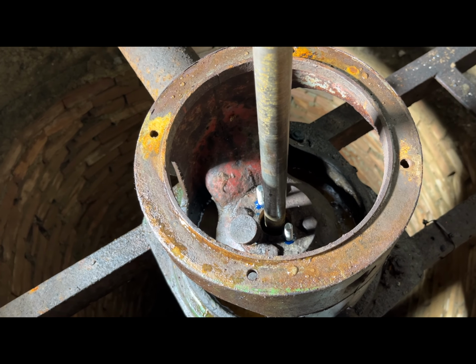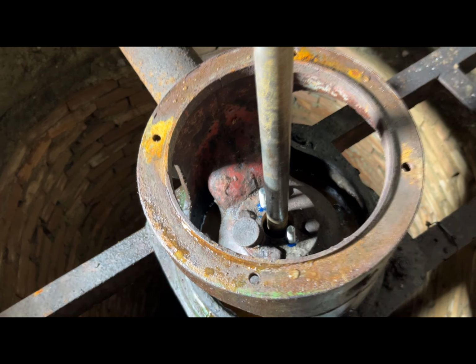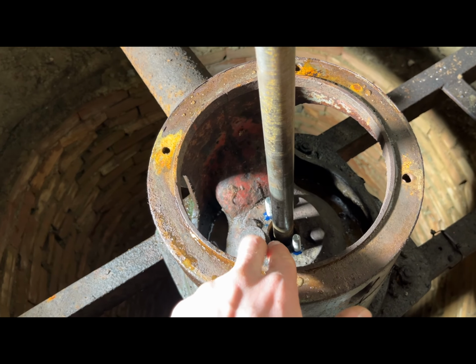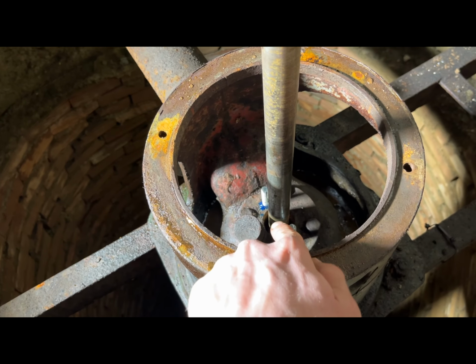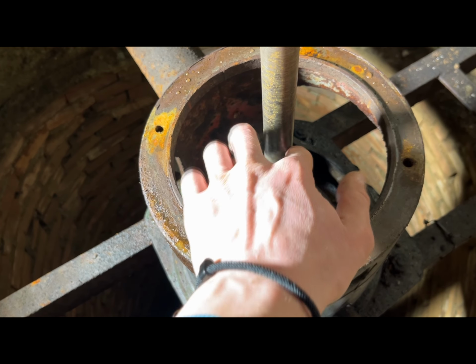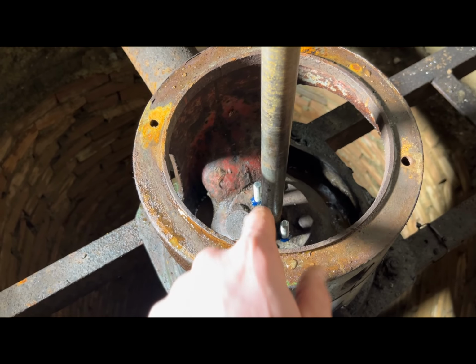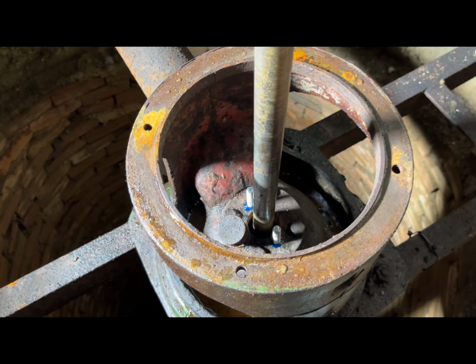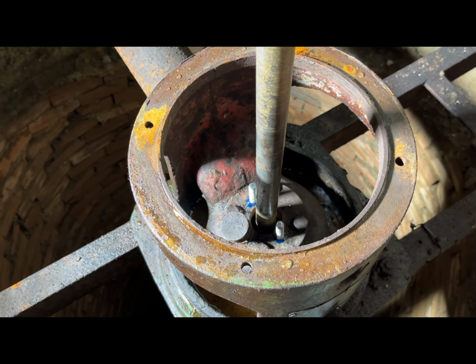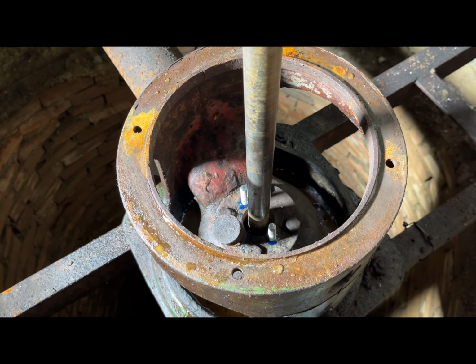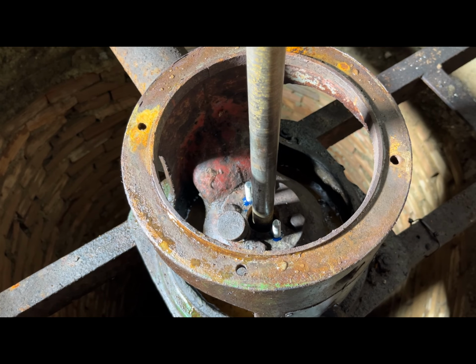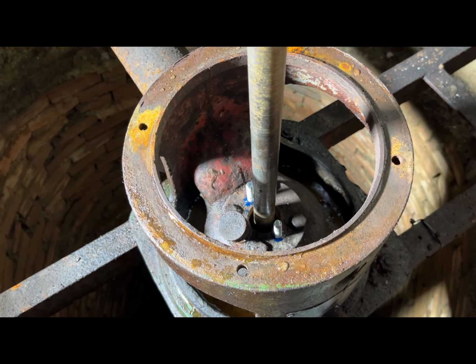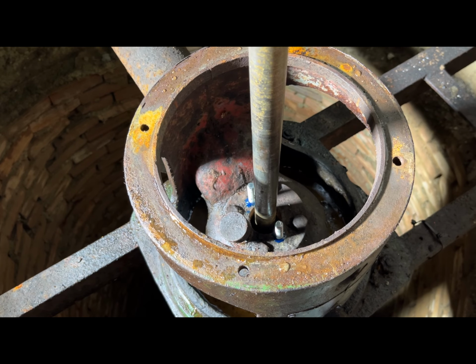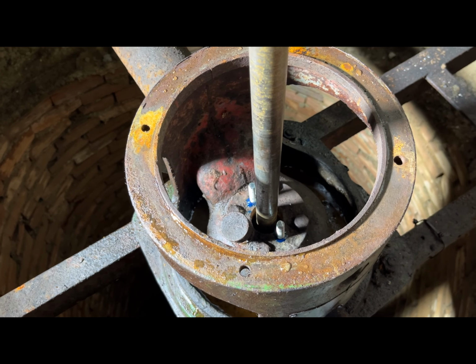Basically what you need is the size of your packing. So you want the outer diameter and the inner diameter of the shaft - the bore and the shaft. Then you subtract the shaft diameter from the bore diameter, and divide it by 2. That gives you the thickness of packing you need to buy.